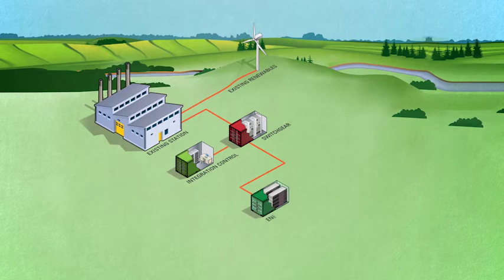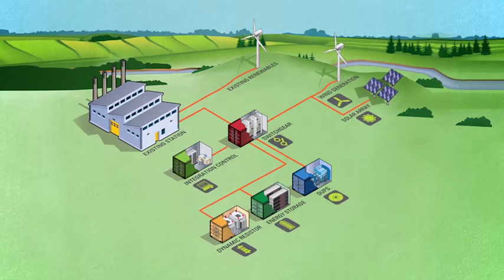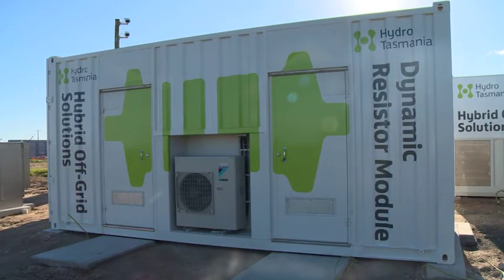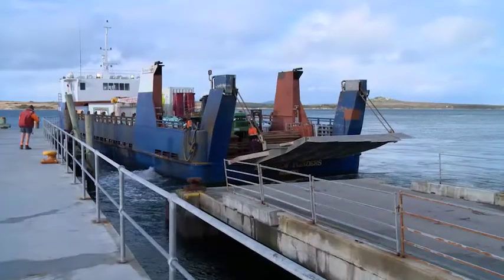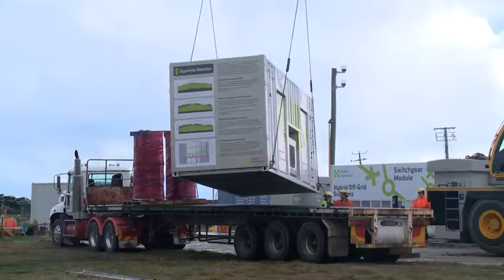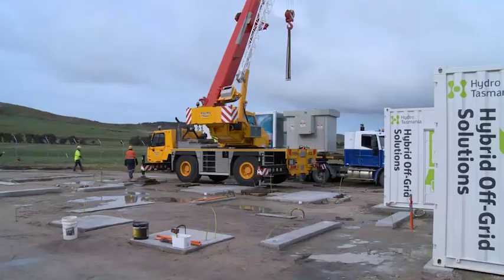The unique nature of the scalable modular system is the ability to test and assemble those systems and be sure that when they arrive on site, they're going to work. We need to get that equipment to these island locations, so we've designed them with a specific format in mind — the 20-foot shipping container. We could test it off site before it came to remote places like Flinders Island, then put it onto a boat all the way over from Tasmania. We truck it from the port to site and unload it using a crane. It can go anywhere we can get a truck with a crane or a side shifter, and our commissioning process should be a lot shorter because we've delivered a product that can simply be plugged together and commissioned.